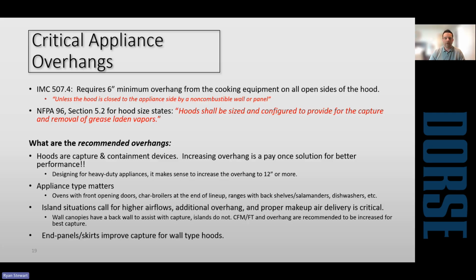So you're going to want to look at those plans or talk to your customer and figure out what appliances are going to go under their hoods. Ovens, you think, are kind of a lighter duty appliance, but with the front doors on those, when you watch them operate and they load and unload product from the ovens, that heat plume will come out 18 to 24 inches. So it's important to have as much overhang as you can for that situation.